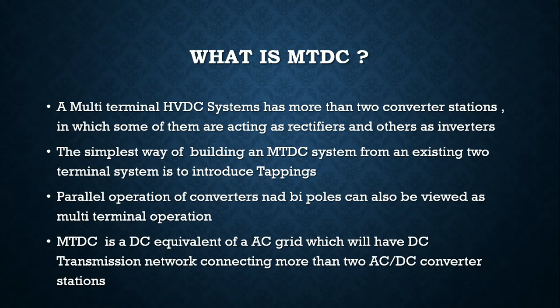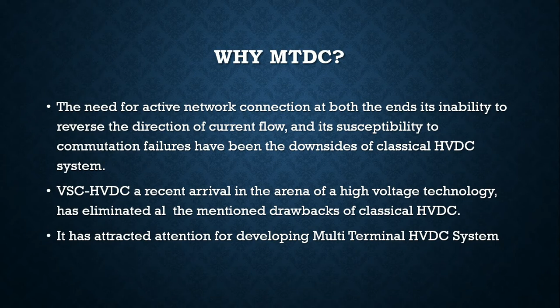Next, let us see why MTDC. The need for active network connection at both the ends, its inability to reverse the direction of current flow, and its susceptibility to commutation failures have been the downsides of a classical HVDC system. VSC HVDC, a recent arrival in the arena of high voltage technology, has eliminated all the mentioned drawbacks of classical HVDC. It has attracted attention for developing multi-terminal HVDC systems.